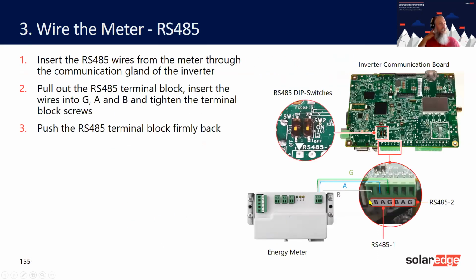B, A, G cables, this is on the communication board I first showed you with two communications here, so 1 and 2. And remember the dip switch is here. So you would need to switch it on if you were using this one here. So switch it on. And then you've got your blue and white here, and then you've got your G. So they are your B, A and G communications.